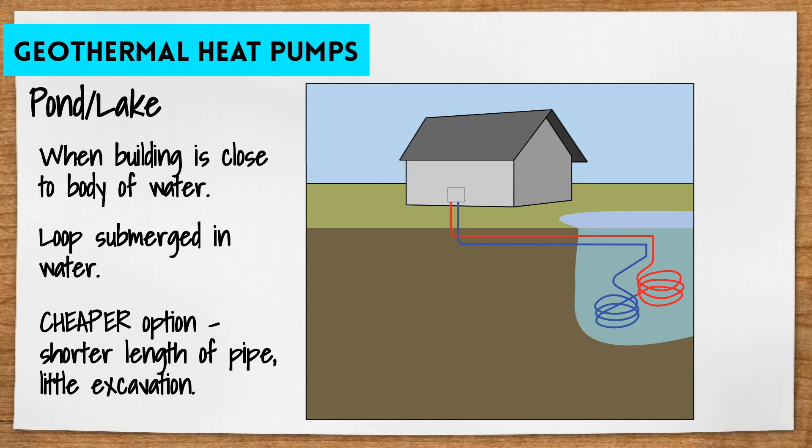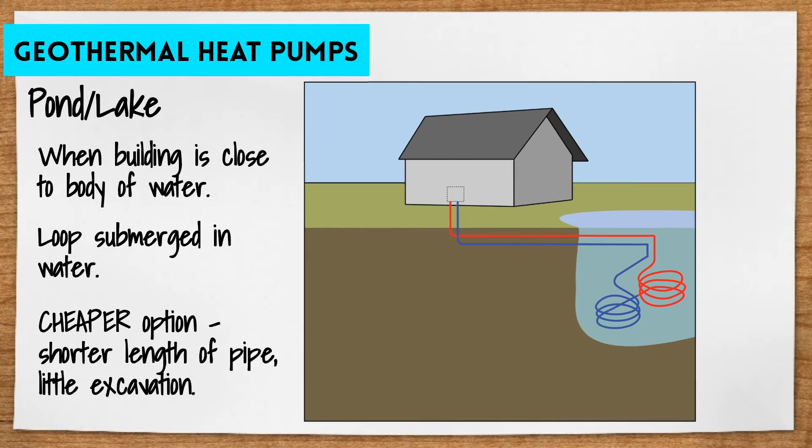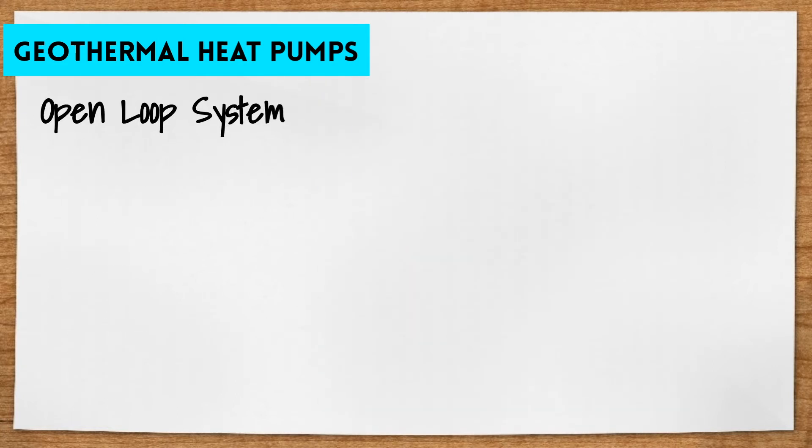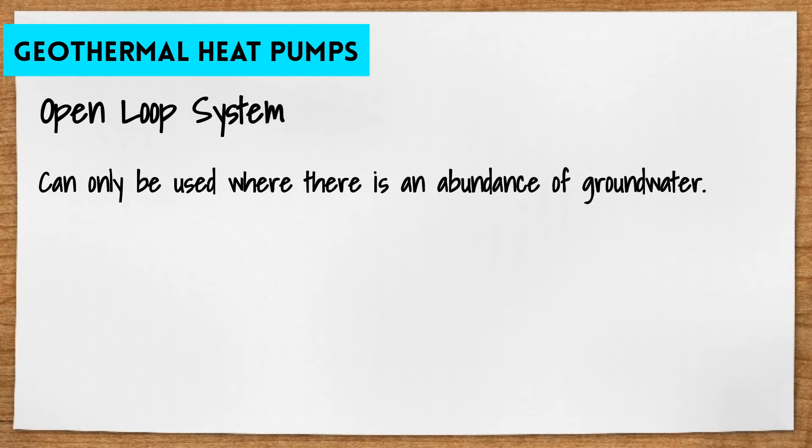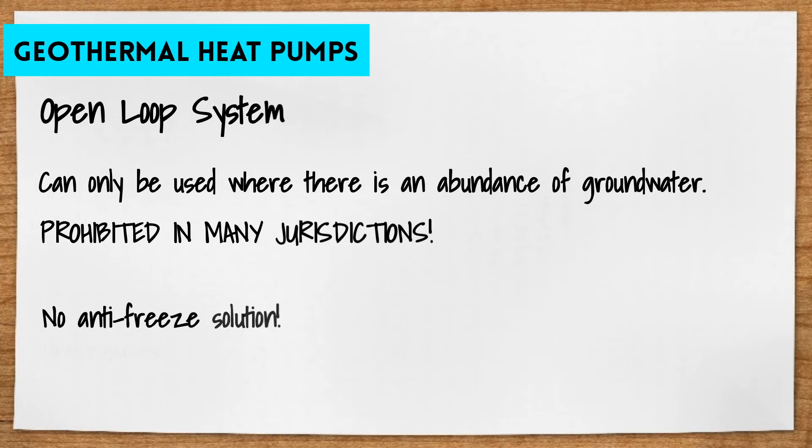The fourth option is an open loop system. This type of system can only be used where there's an abundance of groundwater and is often prohibited by many jurisdictions. The open loop system uses underground well water as the heat exchange fluid that circulates directly through the geothermal piping system.